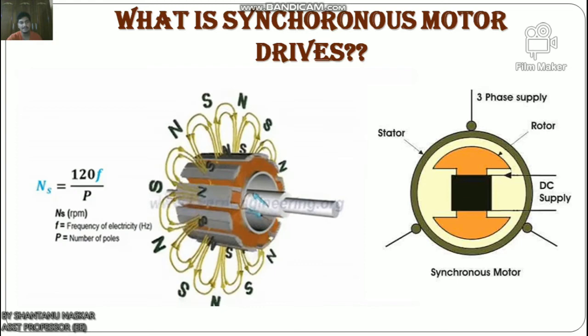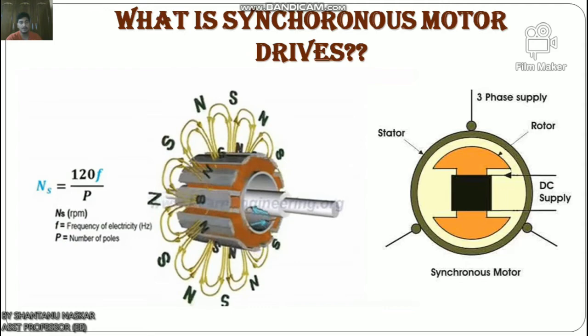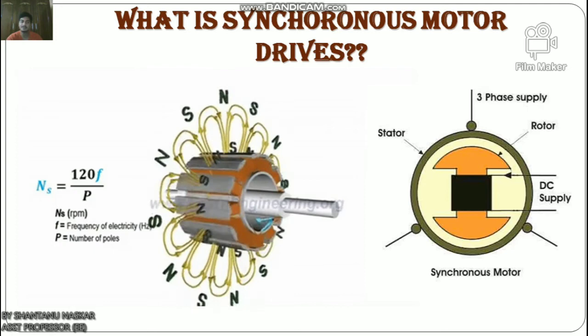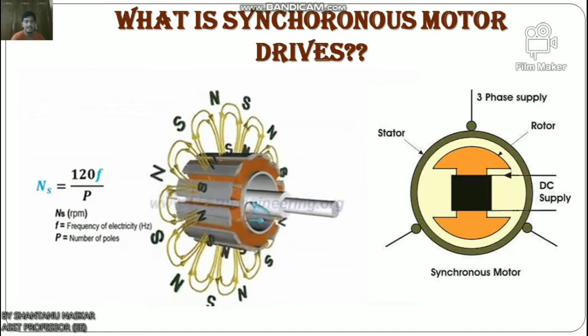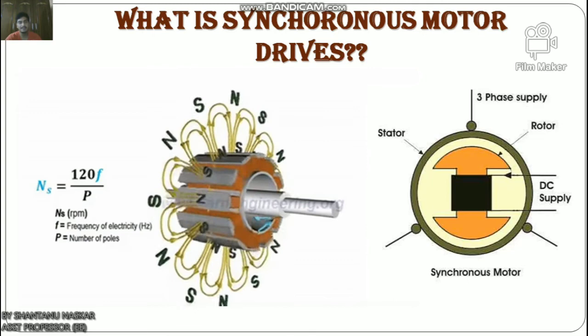Now we will discuss braking of synchronous motors. There are three types of braking: regenerative braking, dynamic braking, and plugging. For synchronous motor drives, only dynamic braking can be applied; plugging can be applied theoretically, but regenerative braking cannot be applied as it needs a higher speed than synchronous speed. Dynamic braking is done by disconnecting the motor from supply and connecting it across a three-phase resistor — at this time, the motor works as a synchronous generator and energy is dissipated in the resistor.